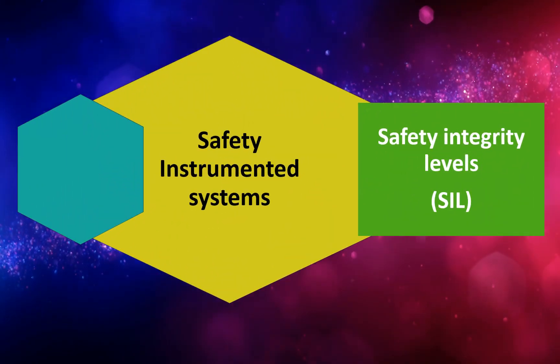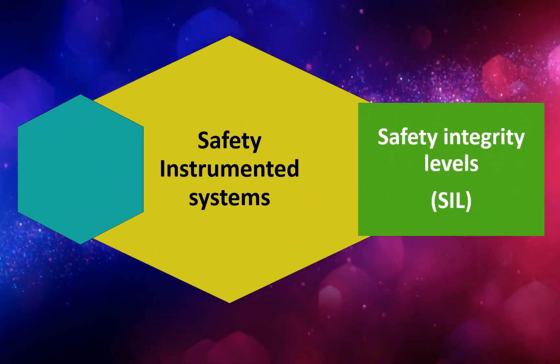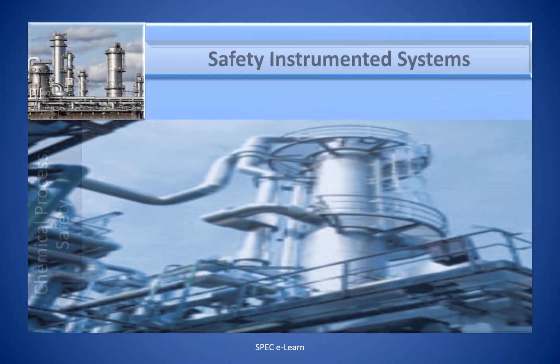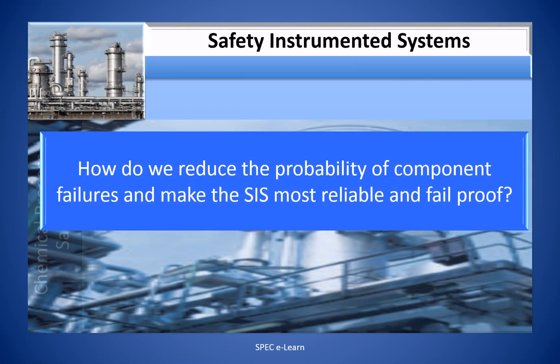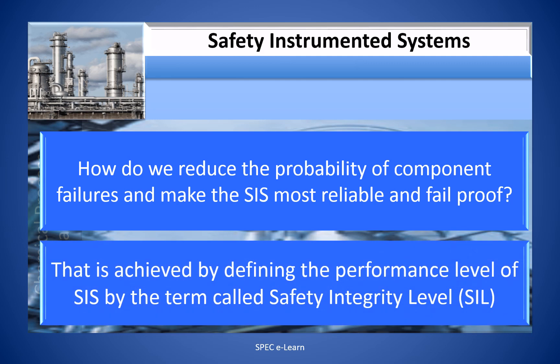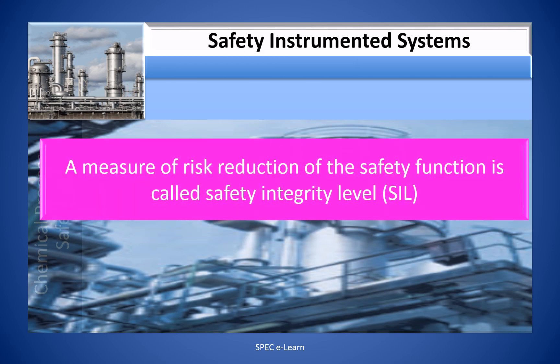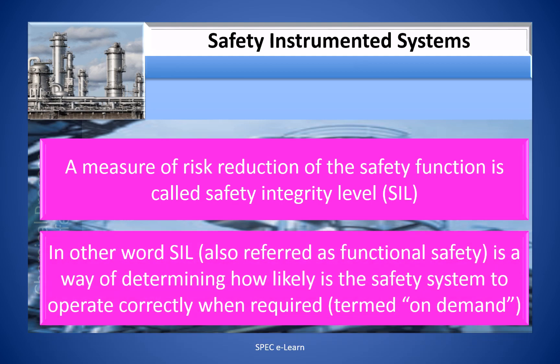Safety Integrity Level. How do we reduce the probability of component failures and make the SIS more reliable? That is achieved by defining the performance level of the SIS using the term Safety Integrity Level, or SIL. A measure of risk reduction of the safety function is called Safety Integrity Level — also referred to as Functional Safety — and is a way of determining how likely the safety function is to operate correctly when required.